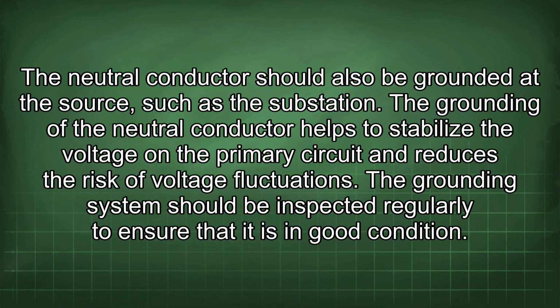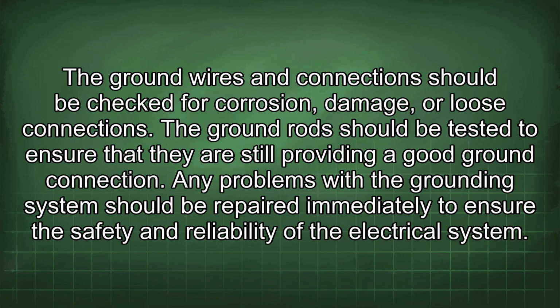The grounding system should be inspected regularly to ensure that it is in good condition. The ground wires and connections should be checked for corrosion, damage, or loose connections. The ground rod should be tested to ensure that it is still providing a good ground connection. Any problems with the grounding system should be repaired immediately to ensure the safety and reliability of the electrical system.